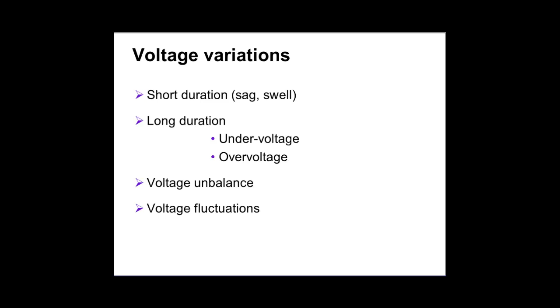If it is long duration, no. So when I say dip, voltage dip, it's not going to be long duration. If I say sag or swell, it's not going to be long duration. So there is a difference between the definitions, because the reason we are separating these definitions from each other is their consequence. The consequence of a sag or swell is much different from a long under voltage or over voltage. That's why. Let's have a look at this and remember this.